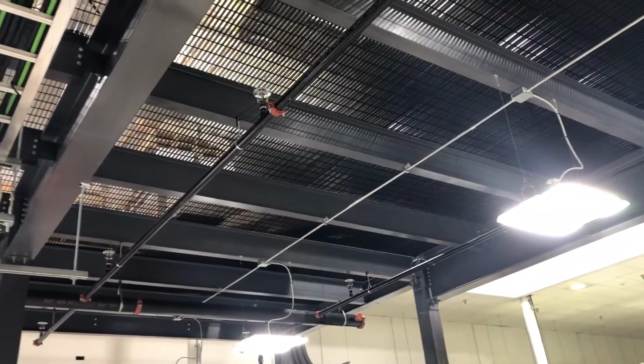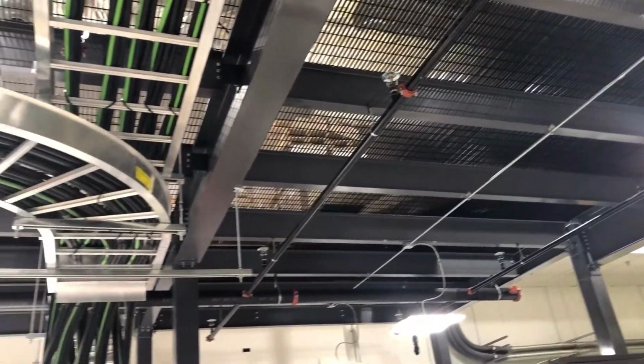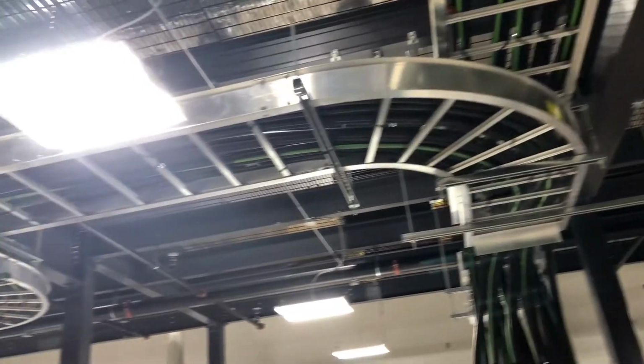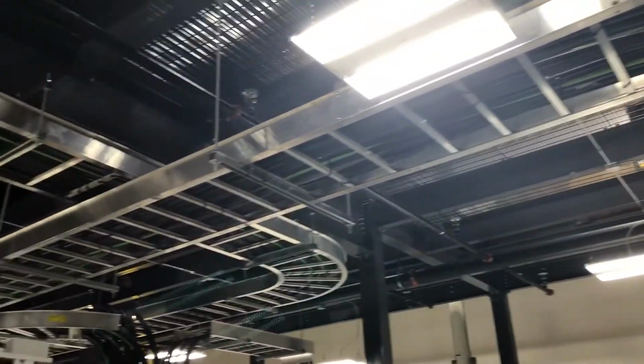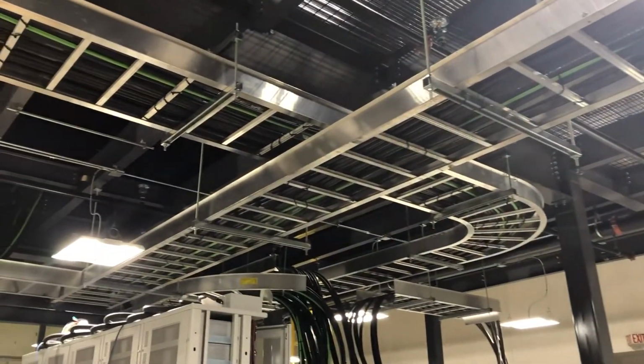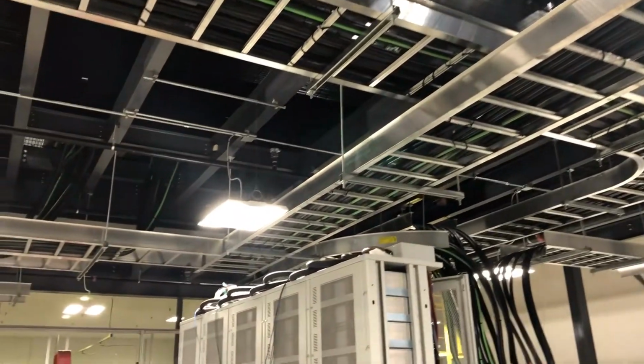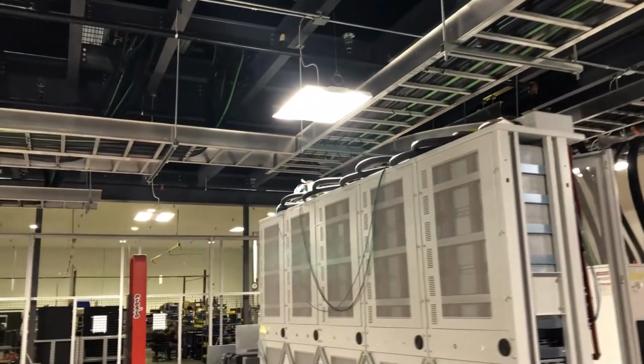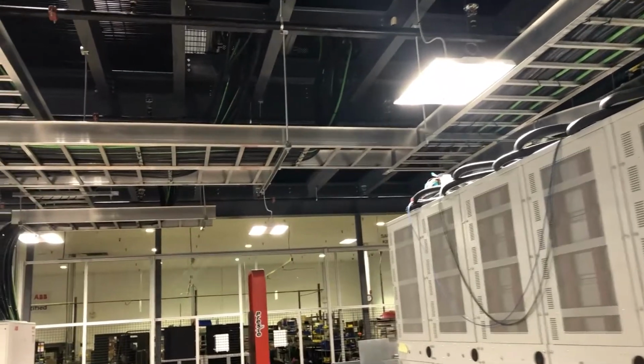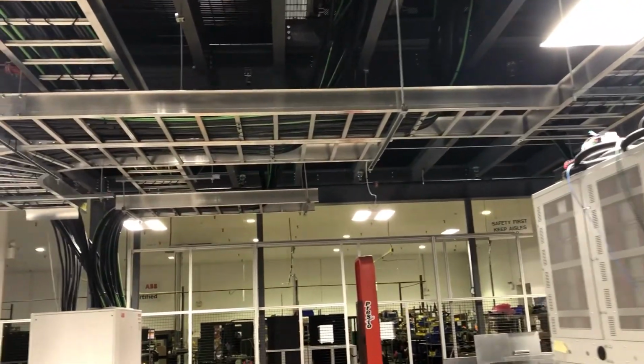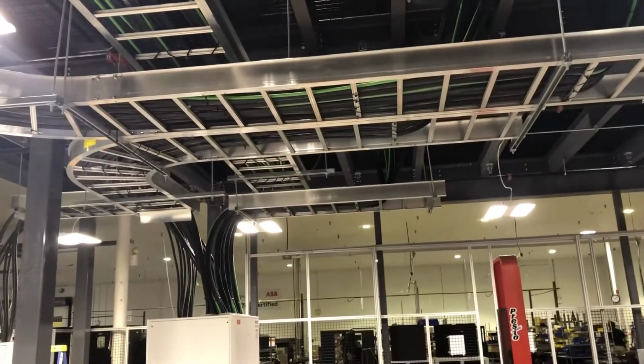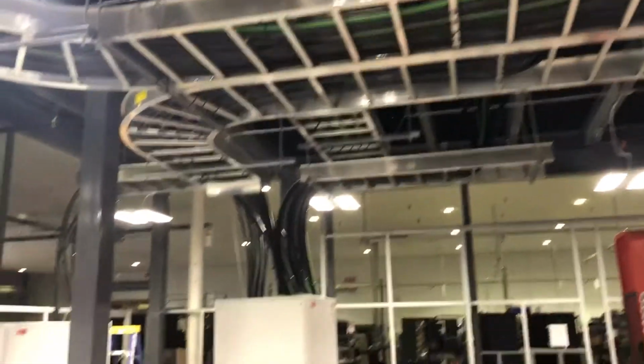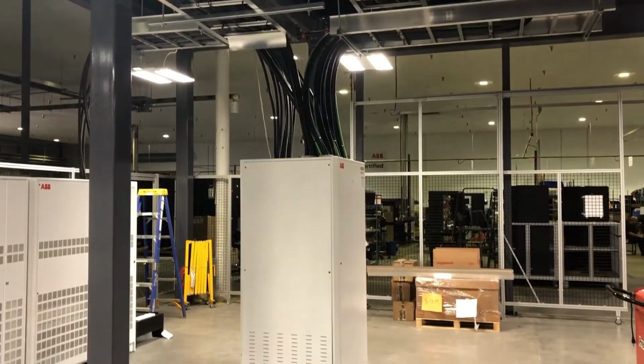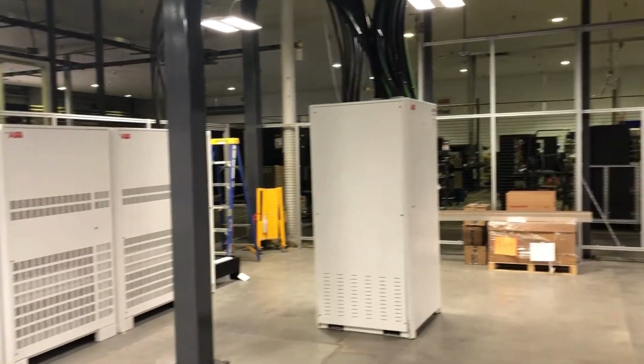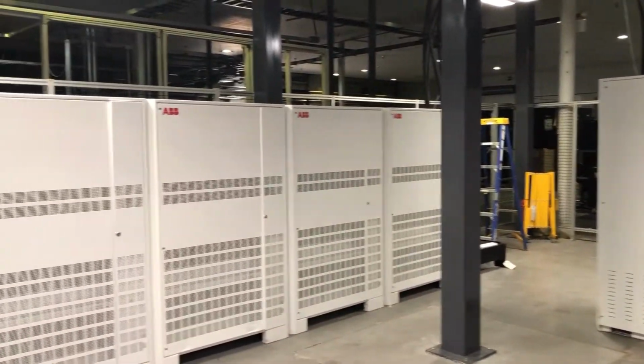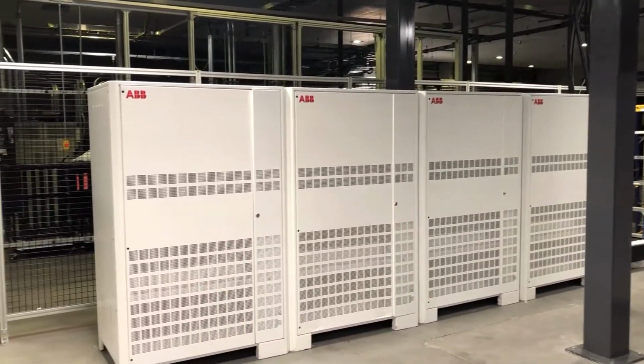In the customer witness test UPS test center, we have a large mezzanine which hosts our input-output switchgear feeding each of the UPS test bays. All of our cabling going to and from the test bays is supported by cable tray. In each of the test bays, we've got a dedicated junction box, which is where we make all of our incoming and outgoing connections, and permanently installed batteries in each of the 4 UPS test bays.